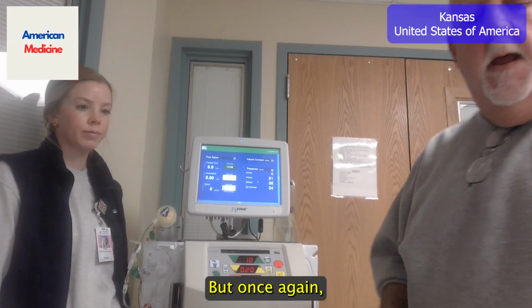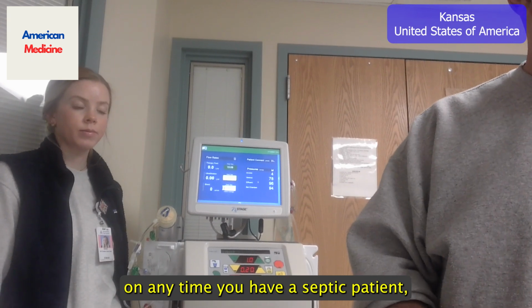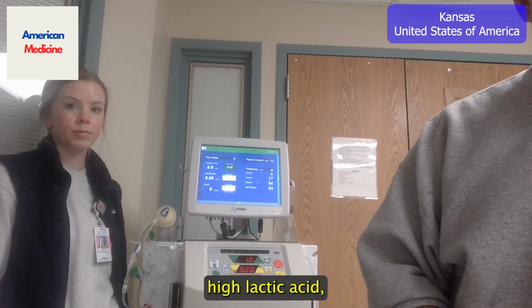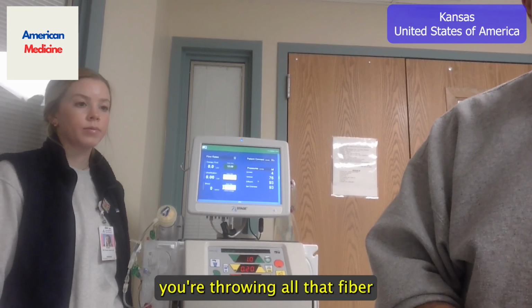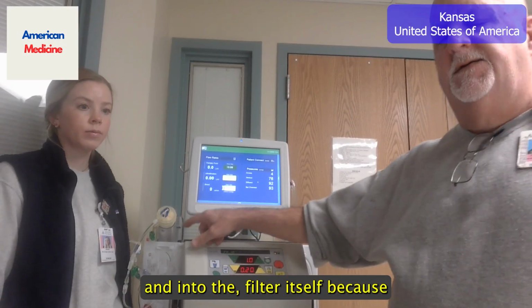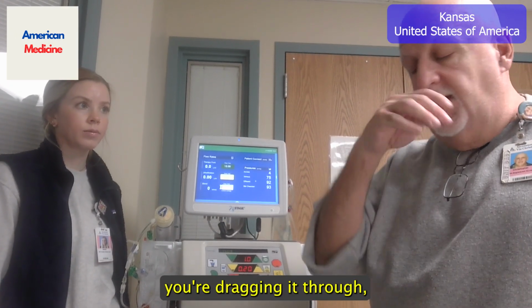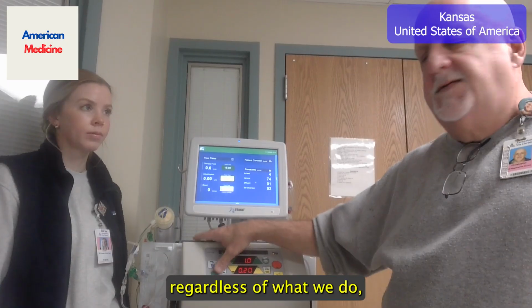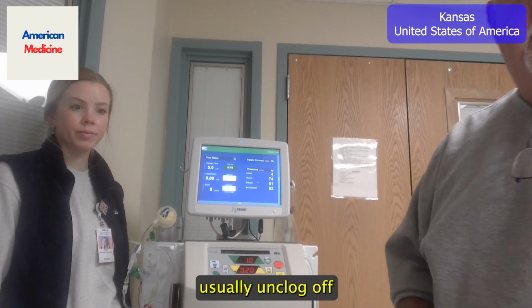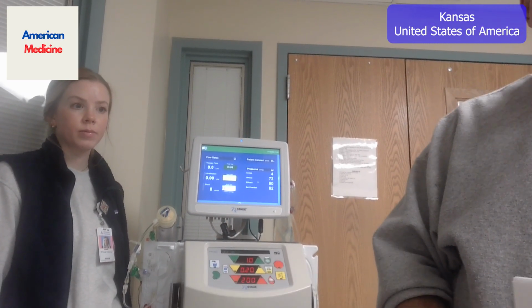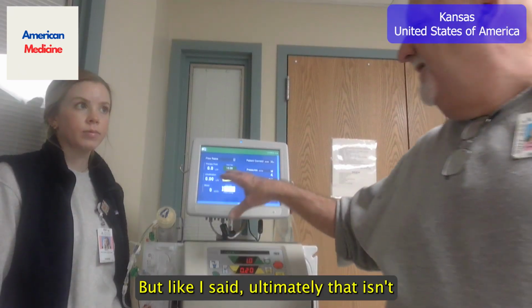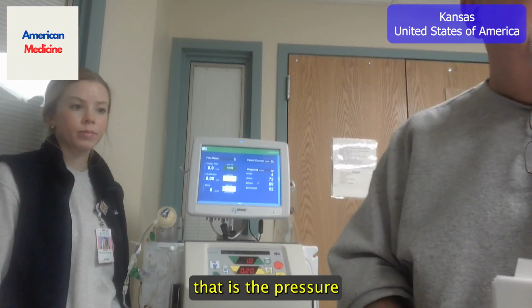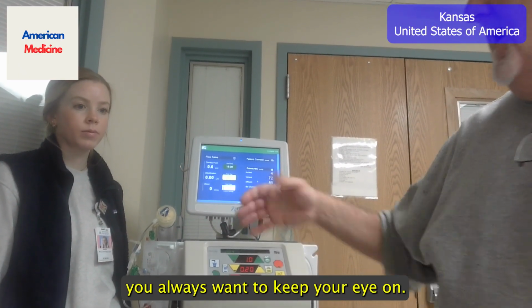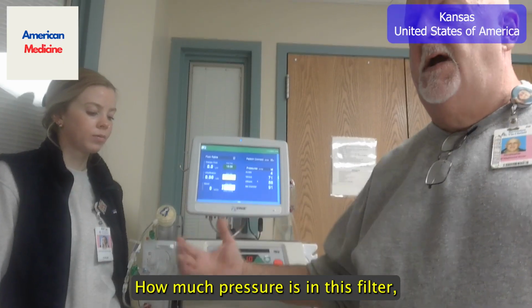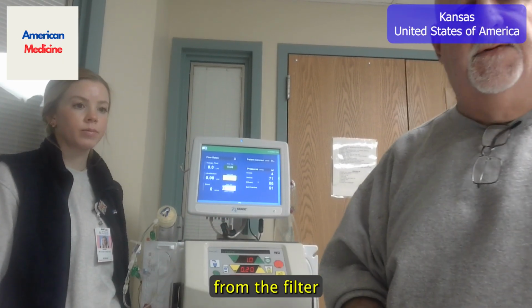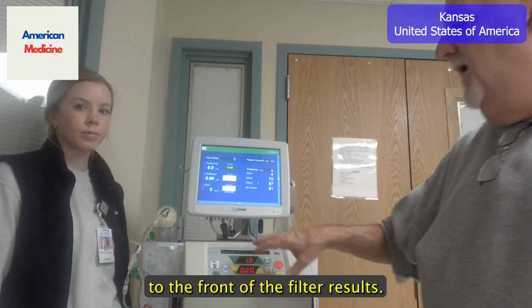But once again, any time you have a septic patient with high lactic acid, you're throwing all that fibrinogen into the filter itself because you're dragging it through. Regardless of what we do, it's usually going to clog off about every 4 to 6 hours. But like I said, ultimately, that is the pressure you always want to keep your eye on. How much pressure is in this filter? How much is it taking to get from the back of the filter to the front of the filter?